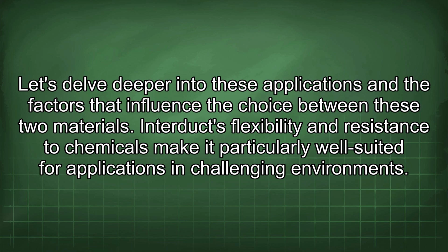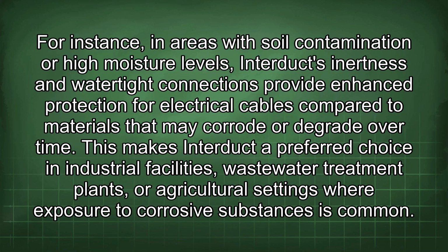Interduct's flexibility and resistance to chemicals make it particularly well suited for applications in challenging environments. For instance, in areas with soil contamination or high moisture levels, Interduct's inertness and watertight connections provide enhanced protection for electrical cables compared to materials that may corrode or degrade over time. This makes Interduct a preferred choice in industrial facilities, wastewater treatment plants, or agricultural settings where exposure to corrosive substances is common.